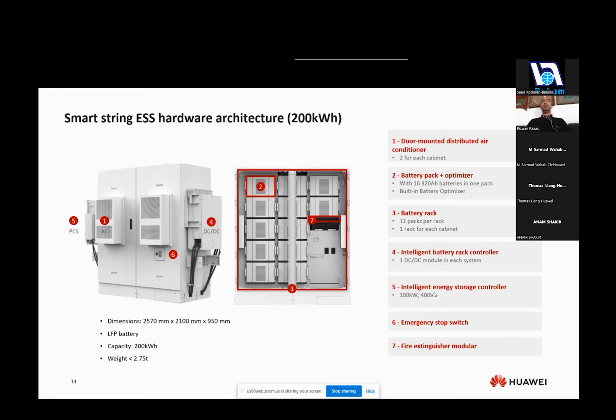So this is mounted and supplied separately and mounted on the exterior mounting brackets of the unit itself. Number 6 is your emergency stop switch, built as standard. And then number 7 is your extinguisher module for any reasons of the product increasing in temperature, which would protect the system itself. So we are using LFP technology, and the capacity is around 200 kilowatt hour in size, and the overall weight with the batteries and the PCS mounted is around 2.7 tons in weight.